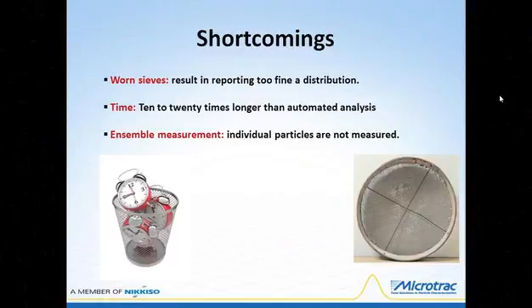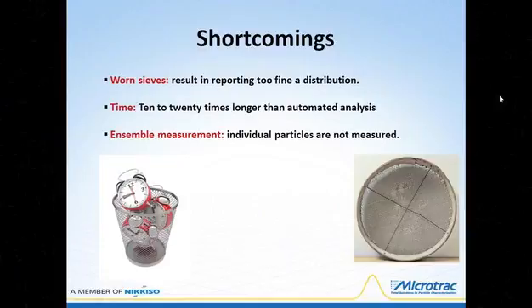Worn sieves are probably the largest source of error in sieve analysis. Working sieve nests wear, resulting in reporting finer and finer distributions over time. Standard procedures require working nests be recalibrated regularly using a calibration nest reserved only for that purpose, but this is seldom done in practice. Sieve analysis requires 15 to 20 minutes to complete including results calculation, considerably longer than computer-automated size analysis. Finally, sieve analysis is an ensemble measurement and cannot report individual morphological parameters on each particle.